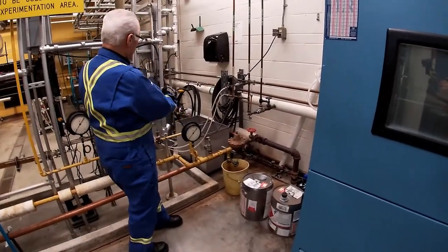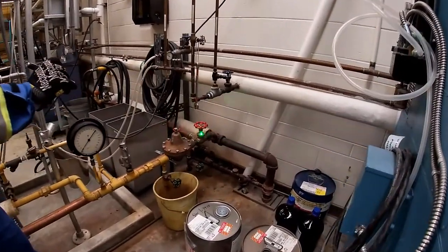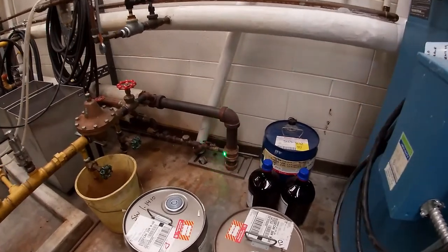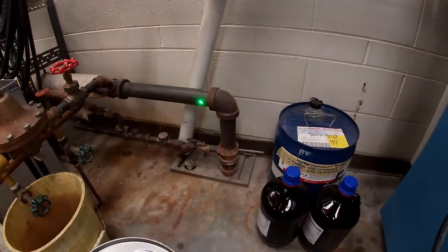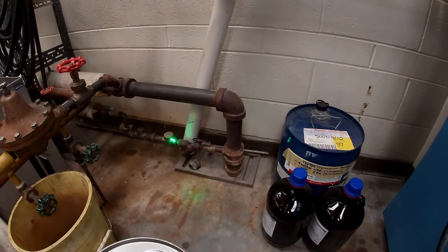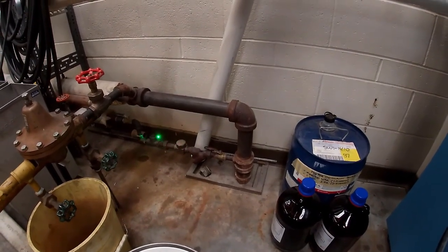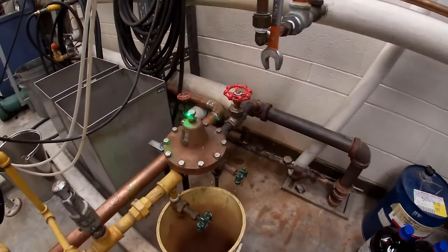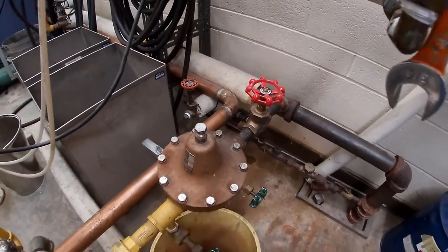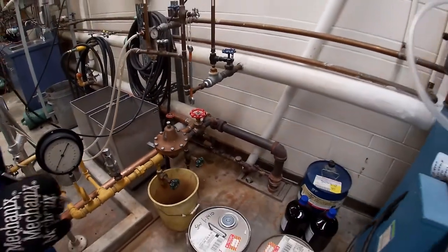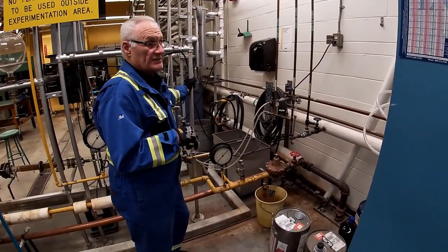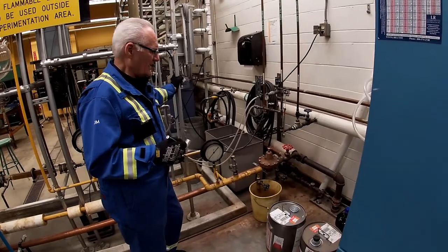Okay, so we're now at the far end of the lab. Here's our steam line coming along the back. And in fact, you can see right here where the line goes down, it's kind of a dead end. It's like what we call a drip leg. So the condensate that's forming will collect in here and then goes through a strainer, and then this is a thermostatic trap, which is then going to feed back to the lower line down there, which is on this line here, and that's the condensate that's going all the way back into the tunnel that runs between the boiler house and here, and then that condensate actually goes back into the steam plant and is reused and made into new steam.